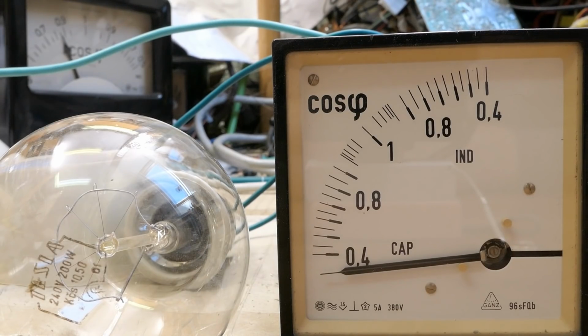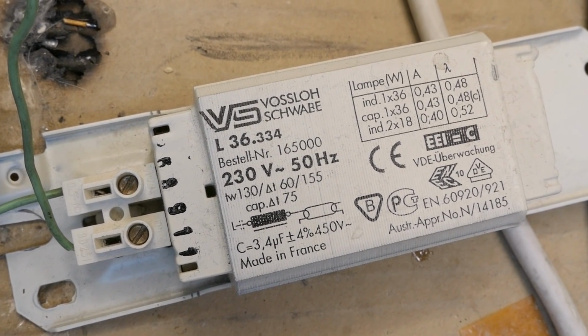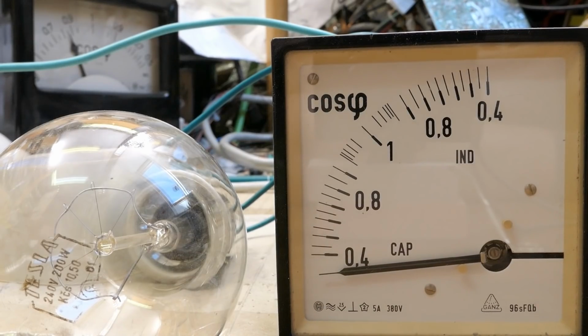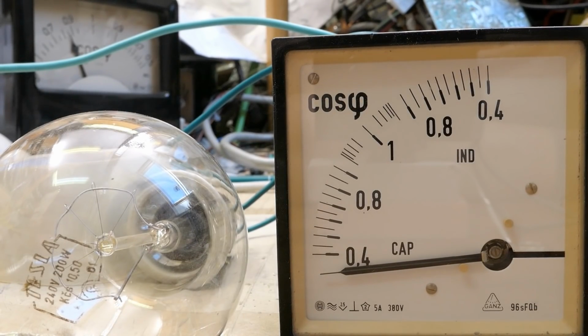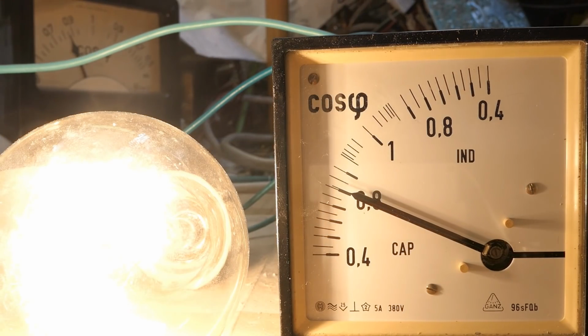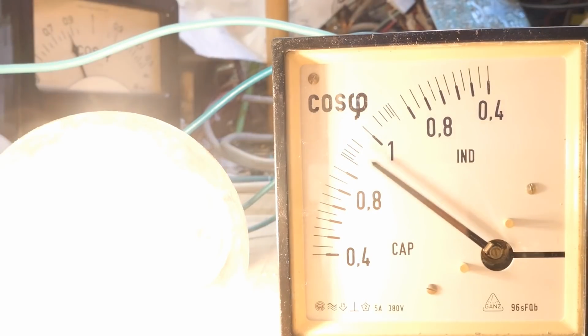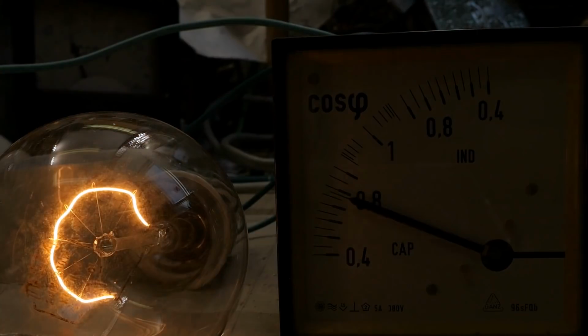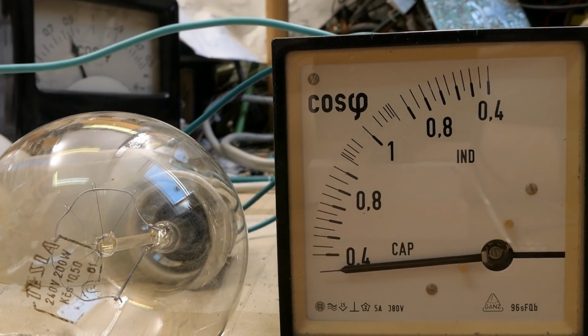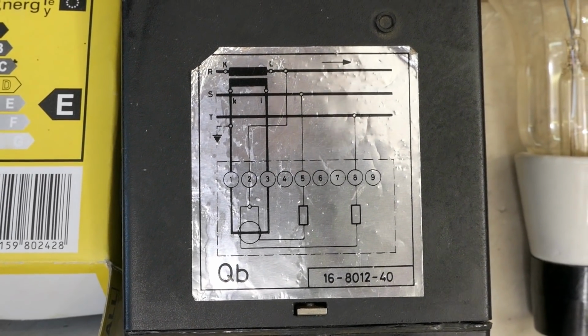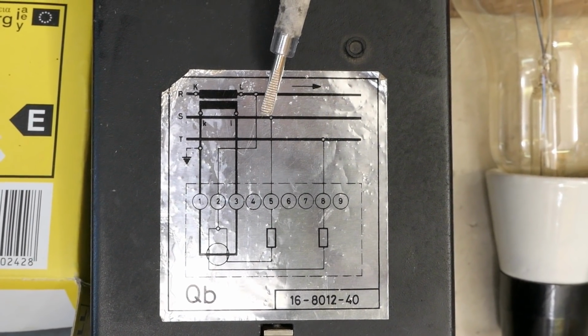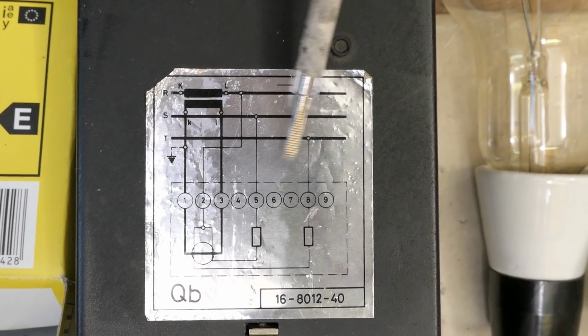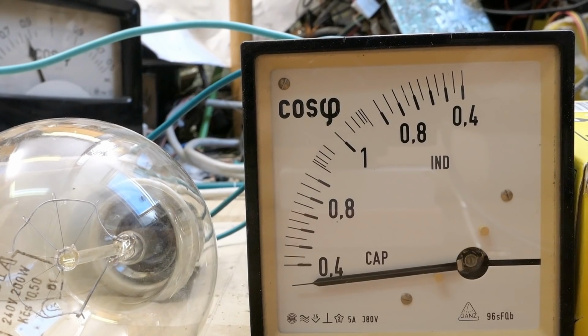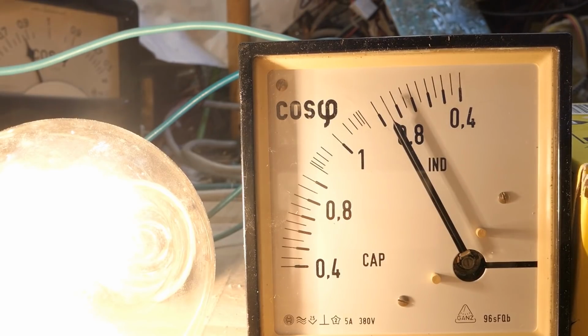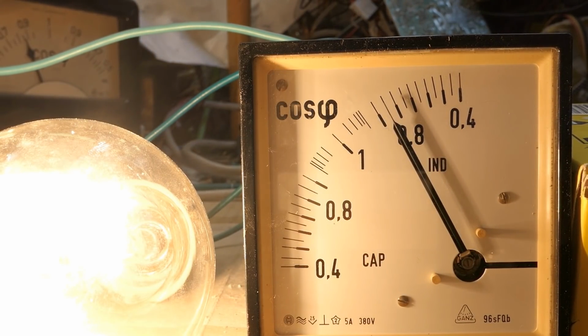so I can't test it using just a capacitor or just an inductor. But let's put a fluorescent inductor in parallel to the lamp. Now it should be partially resistive, partially inductive. So let's power it. And it seems to indicate capacitive. Well, this probably means that my phase order is reversed. The phases are in the wrong order. Let's reverse this phase with this one, the two which go to the resistors. Now the phases are reversed and it's actually showing inductive now, so it's right.